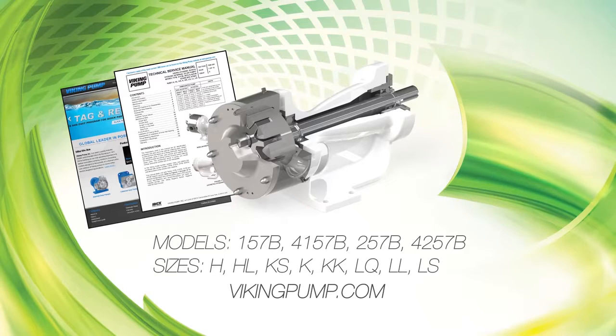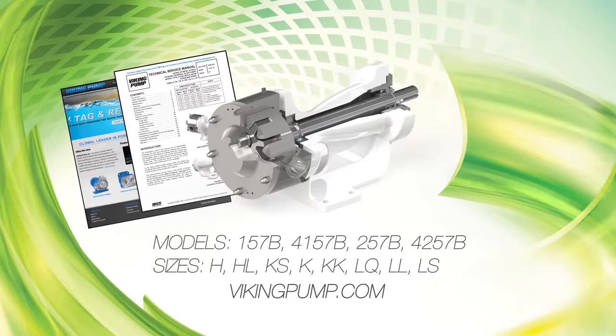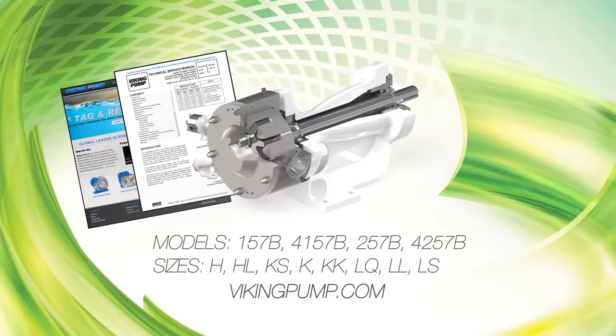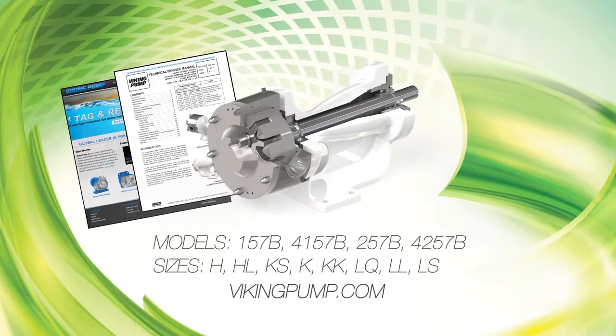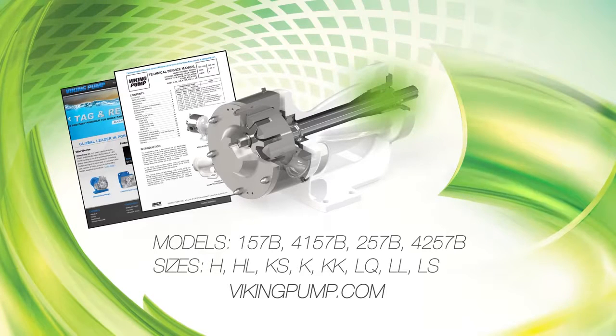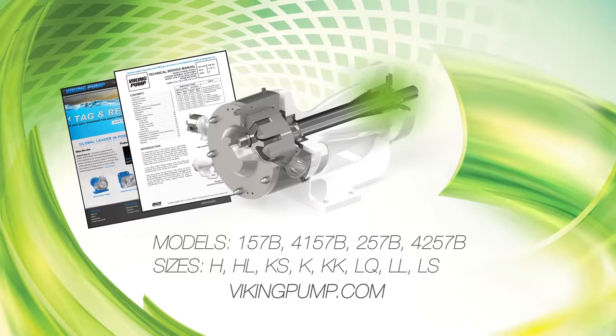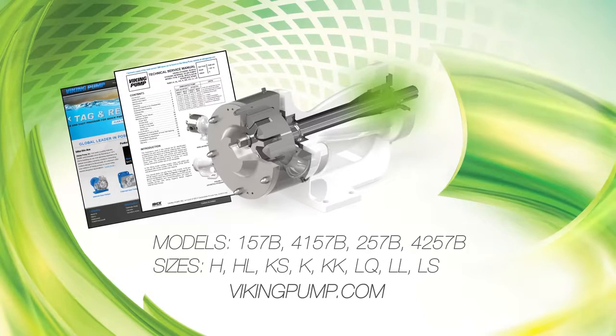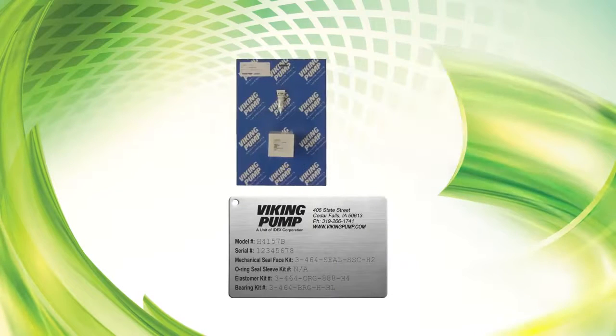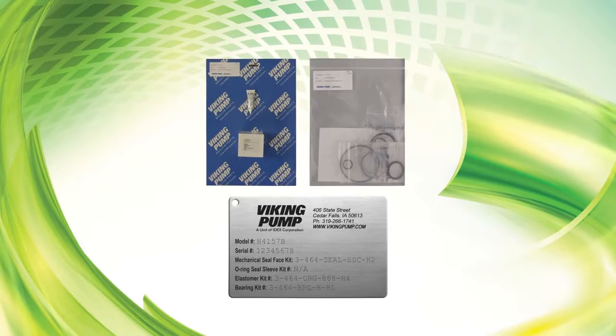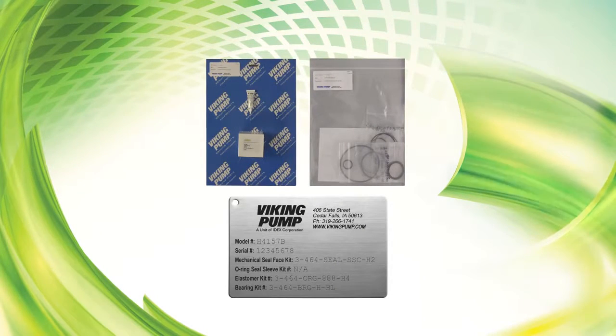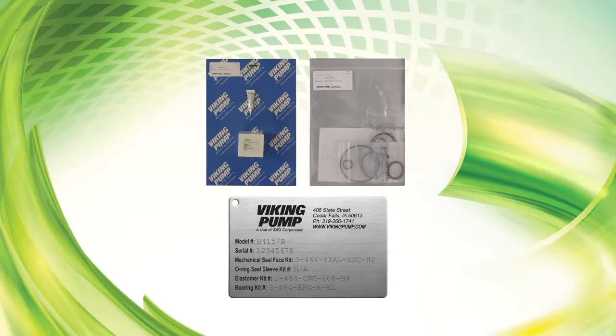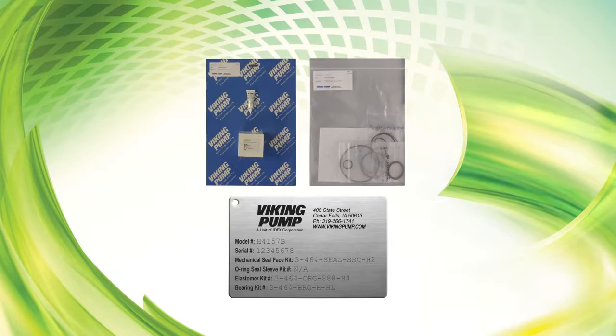It's critical to know what liquid the pump has been handling and the precautions necessary to safely handle the liquid. When cleaning the exterior of the pump, avoid spraying water or cleaning solution directly at the bearings. The seal face kit and elastomer kit part numbers can be found on a hang tag on the pump. If the tag has been removed, contact your local authorized Viking pump distributor to obtain these kit numbers.